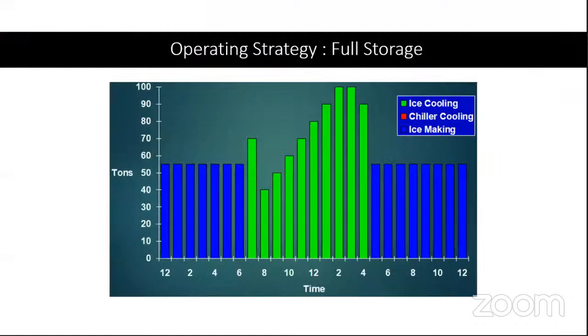Based on that, we need to arrive at the operational strategy. What is going to be the operational strategy? There are generally three operational strategies. Here, these are 24 hours, and these green bars show that thermal storage was used. At night time, these blue bars are for chillers. So chillers stored the thermal energy at night time, and during the day operational hours, the thermal energy storage was used the entire time. This is called the full storage operation strategy.